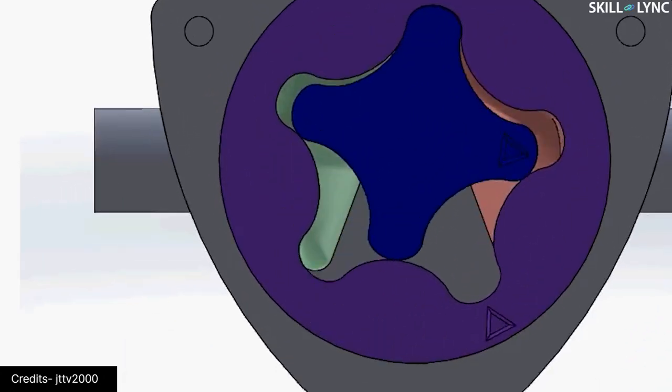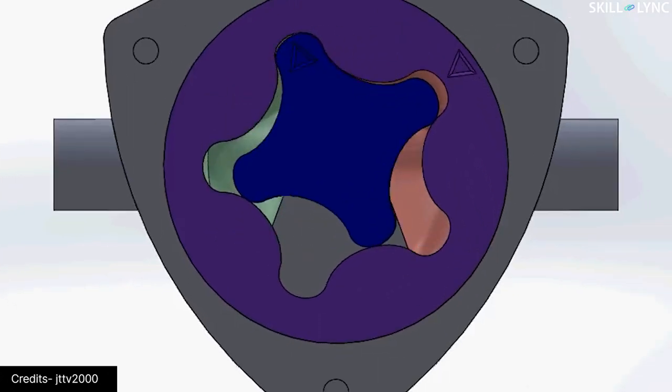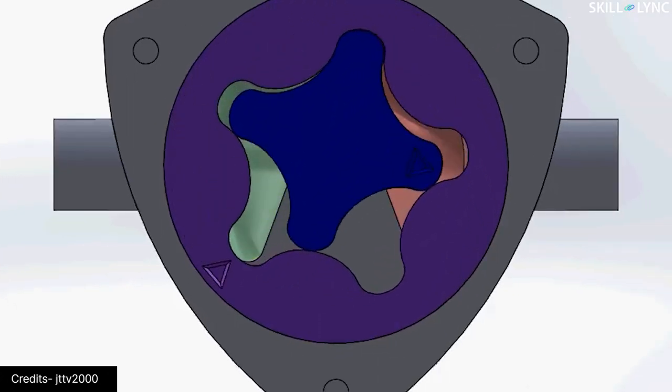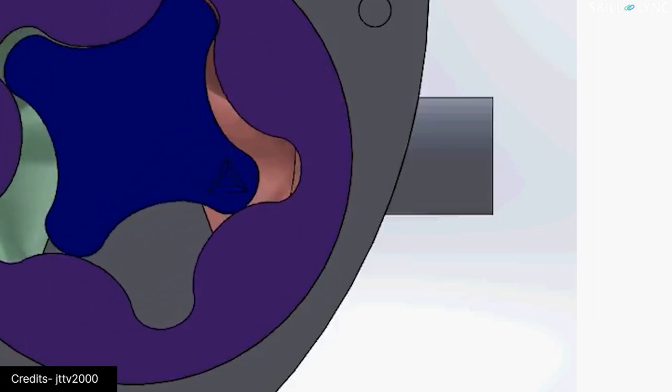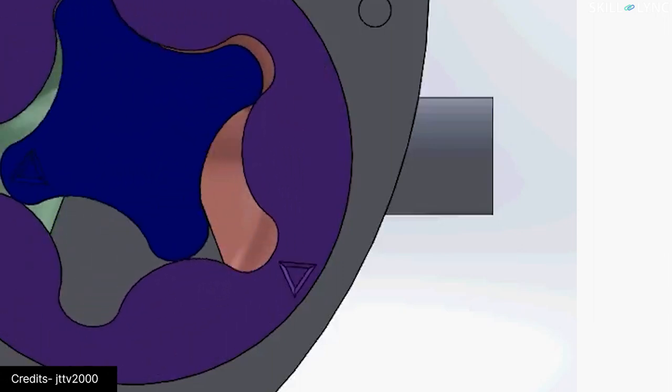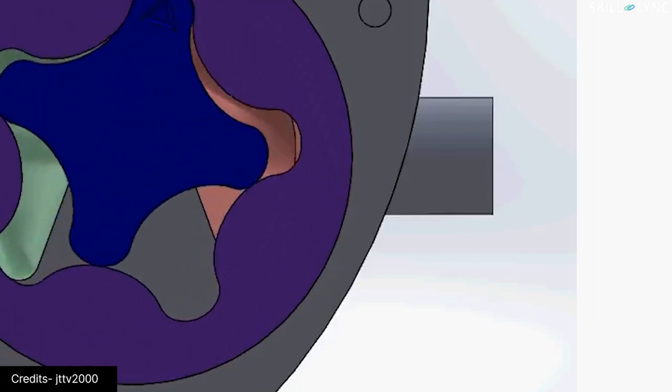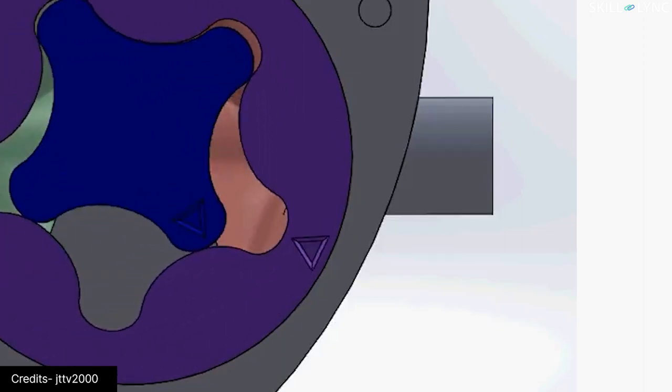The fluid enters the gerotor through an inlet port. The fluid is then transported to the discharge port by the internal gear. Once the fluid is at the discharge side, the area between the two rotors decreases due to its shape. This forces the liquid out through the discharge port.